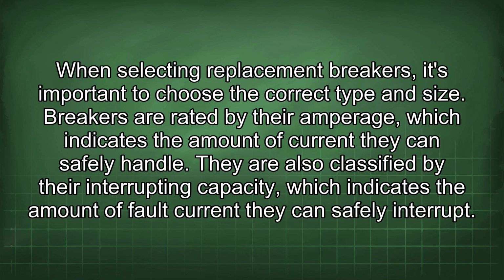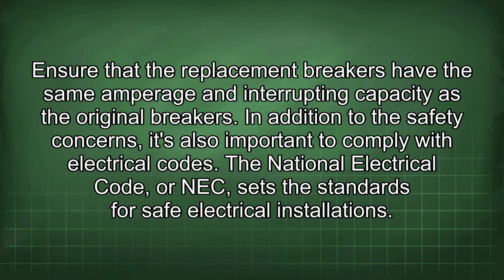When selecting replacement breakers, it's important to choose the correct type and size. Breakers are rated by their amperage, which indicates the amount of current they can safely handle. They are also classified by their interrupting capacity, which indicates the amount of fault current they can safely interrupt. Ensure that the replacement breakers have the same amperage and interrupting capacity as the original breakers.